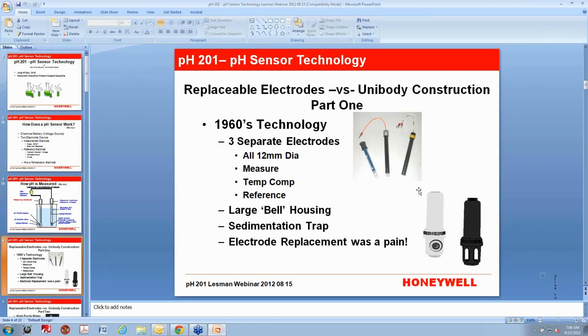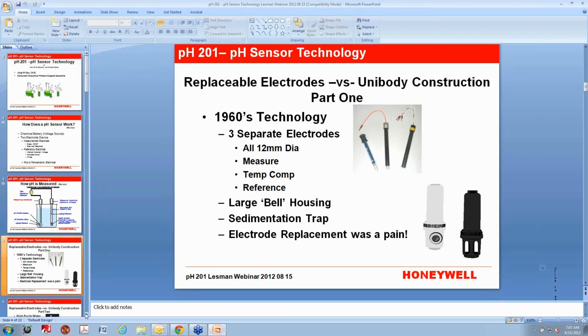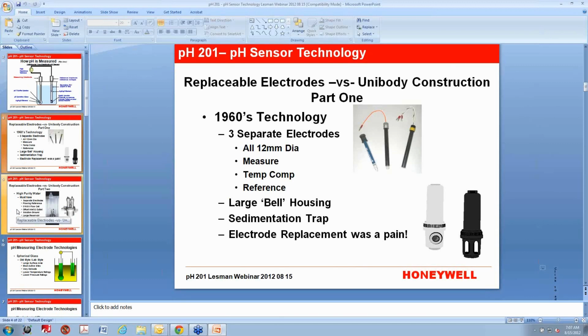But you have all these O-rings to deal with and whatnot. It's a little bit of a complicated process. And they tend to be a sedimentation trap in your process because you have those 3 electrodes hanging out, and then you have this protective cover on them. So if you have a process that tends to foul things up, it's definitely going to get stuck on these 3 sensors. And it was just sort of a pain to replace the electrodes. So as time went on, and we got better at making pH sensors.